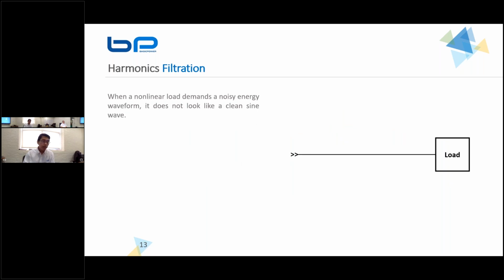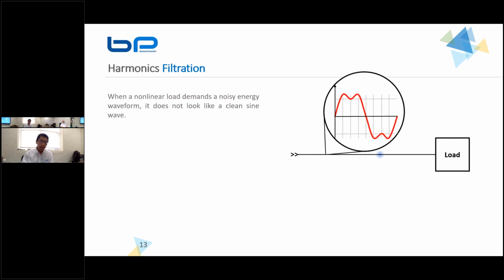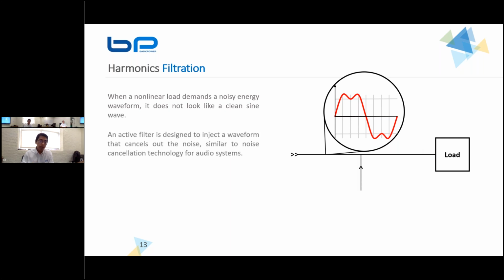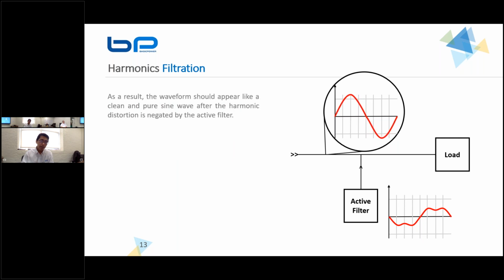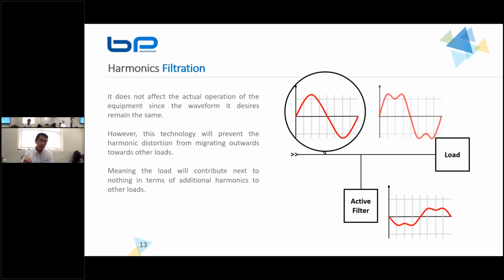Now, to mitigate this problem, people generally use harmonic filtration. If you look at this example here, you see that humpback 6-pulse waveform, and that's what the load is demanding. A way to fix it is to put in something like an active filter. It measures the actual waveform and creates an opposite waveform. This opposing waveform is added to the original, or in this way actually subtracted, and you end up getting a sinusoidal waveform when you measure again from that same point. Note that this isn't changing the waveform of the load, because the load is still demanding the same exact waveform. It's just that the harmonics won't go back to the rest of the distribution system. You'll measure a clean sine wave from upstream while allowing the downstream equipment to operate the same exact way.